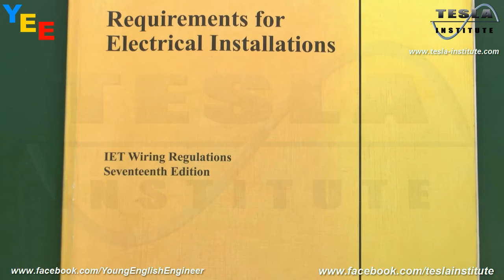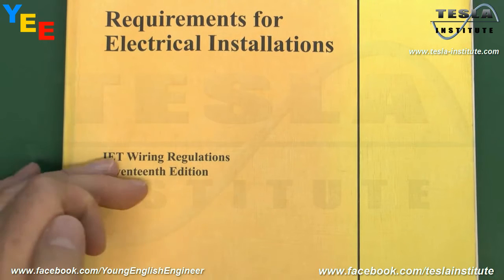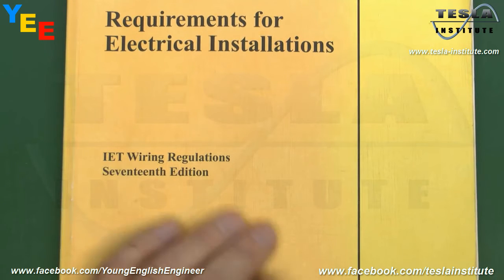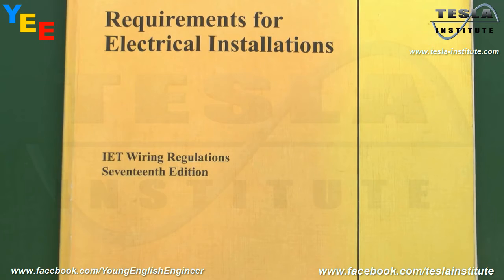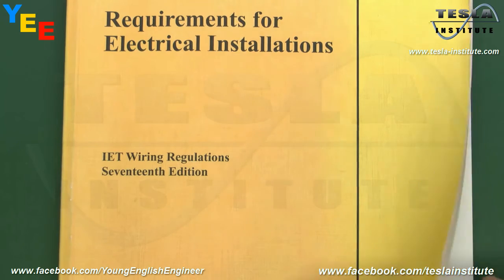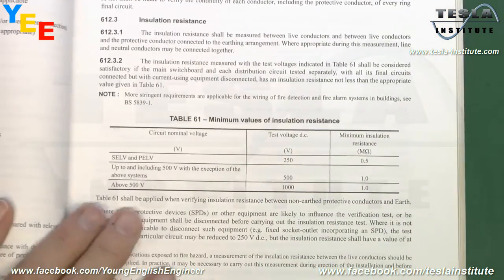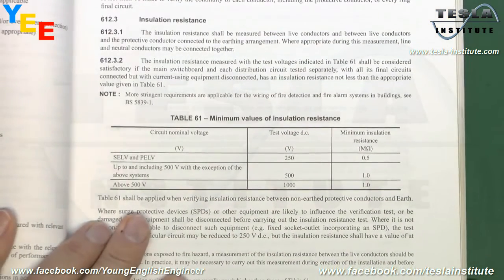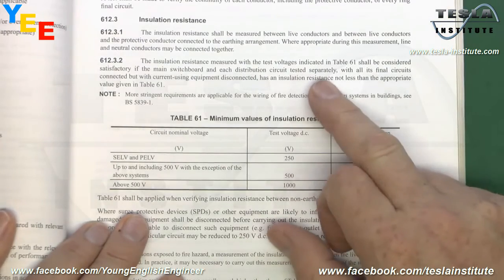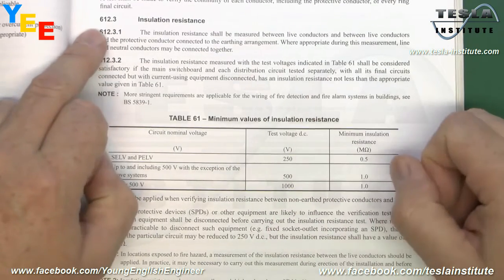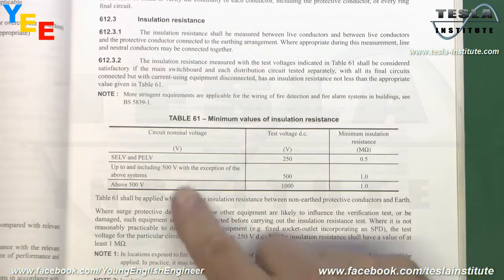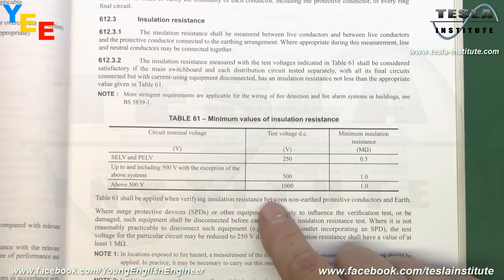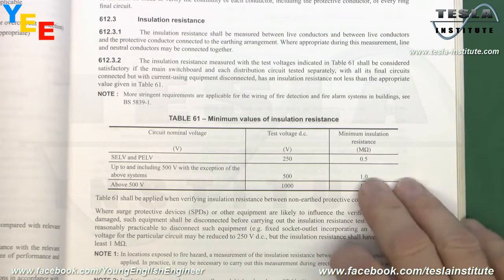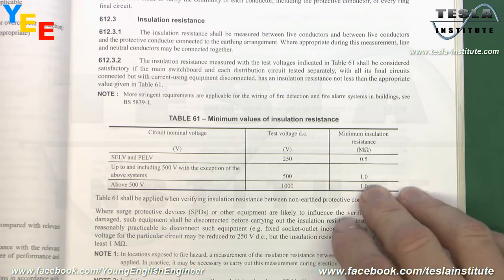The procedure for this test, and in fact all the others, can be found in the Wiring Regulations book here. This is the yellow covered edition, and it's the one in use in 2016 when this video is being made. Obviously in the future the edition will change. Have a look inside here, and there's a whole section on testing, in this particular case section 612. We've got a table here which indicates the various voltages to use and also the minimum insulation resistance that you would expect to find.